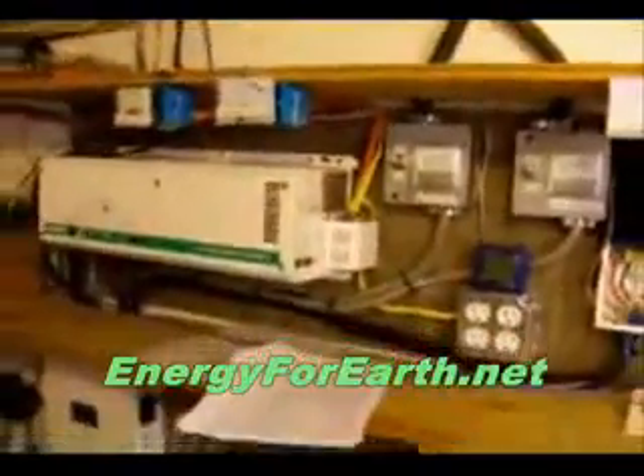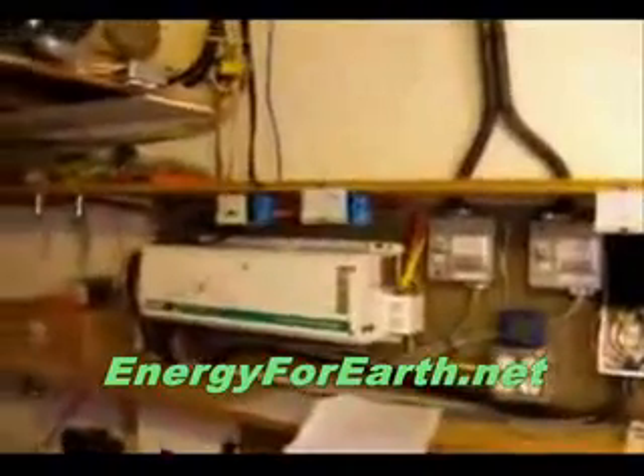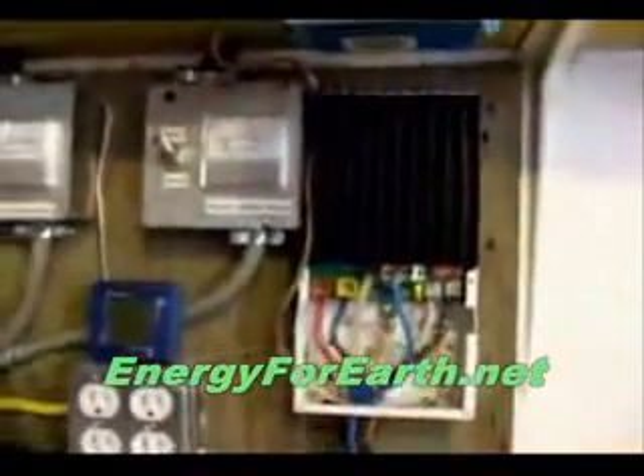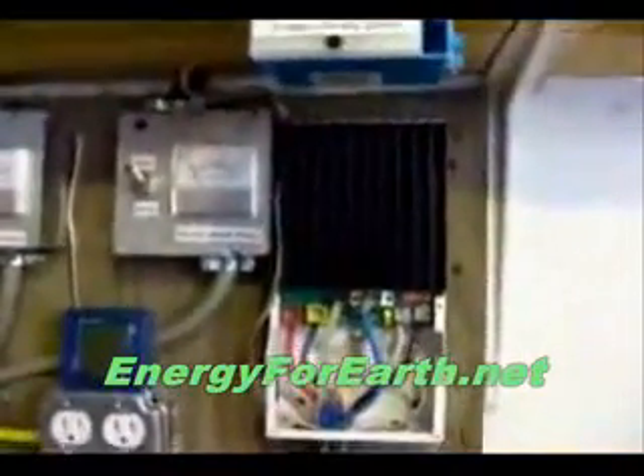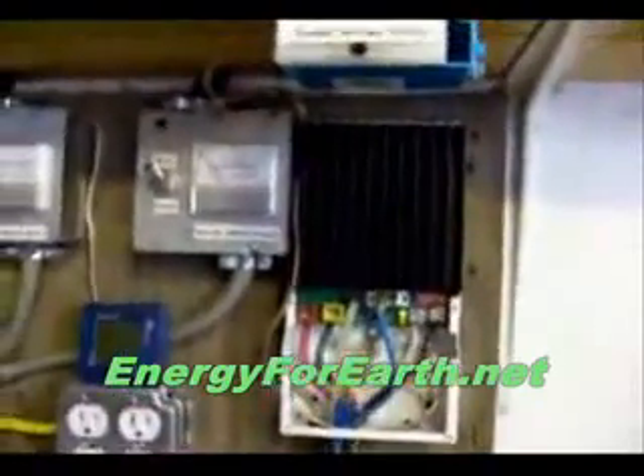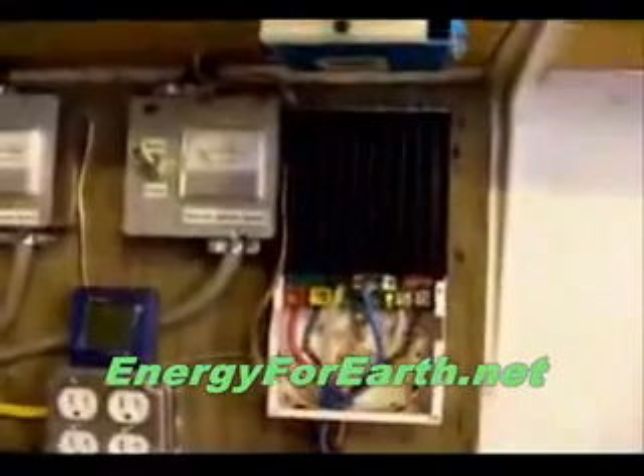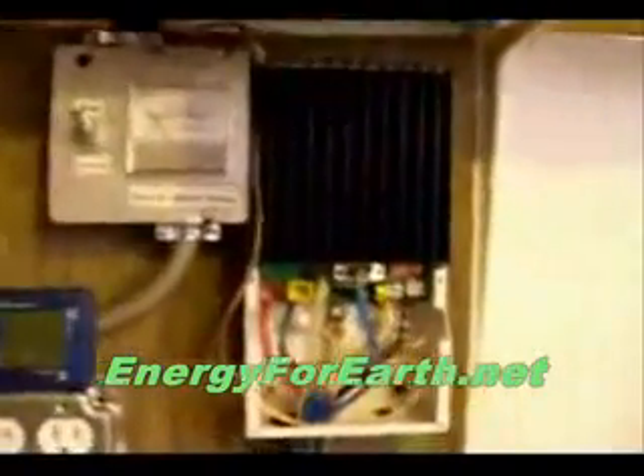Of course, this controller is way overbuilt for what we're doing with it. But most of the equipment in the basement we spent good money on to make it upgradable for the future when we get more wind and or more solar. This controller is actually good for handling up to 4 kilowatts of solar power, and right now we have 0.3 of a kilowatt running through the controller, so we are just teasing it.